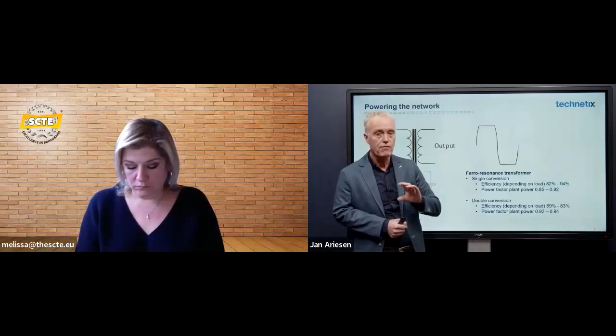The way it's done, mostly, though not always, is by a ferroresonant transformer, a constant voltage transformer. You have your normal transformer, and then you have an extra winding there to saturate the transformer, so that the voltage will not go above a certain level. Therefore, you can see that instead of a sine wave, we are topping off, because at that moment the iron pack gets saturated and will not go any higher than that. There are two ways of doing it. We have single conversion and we have double conversion. They both have their pros and cons.